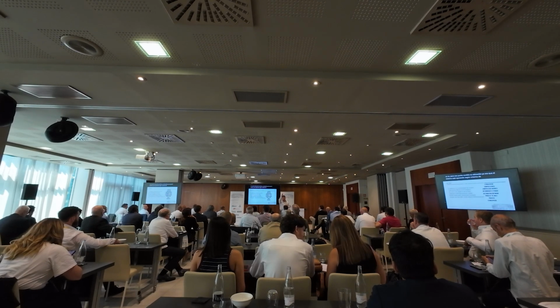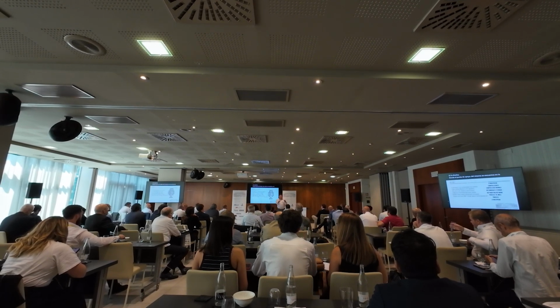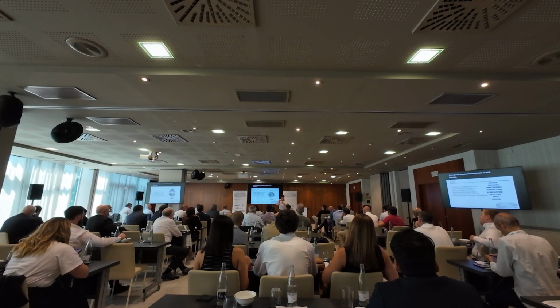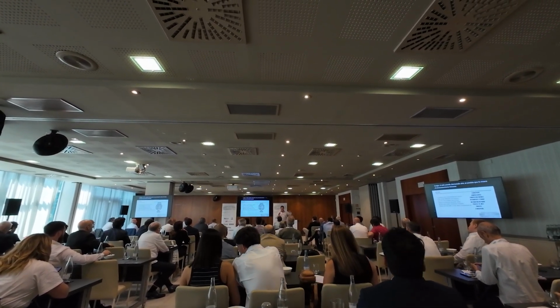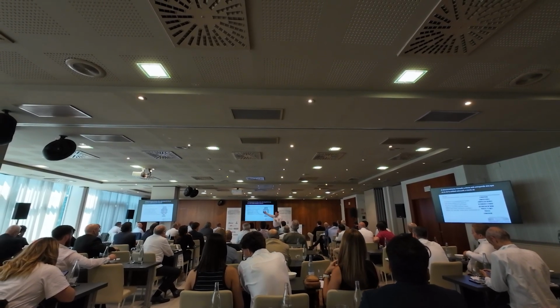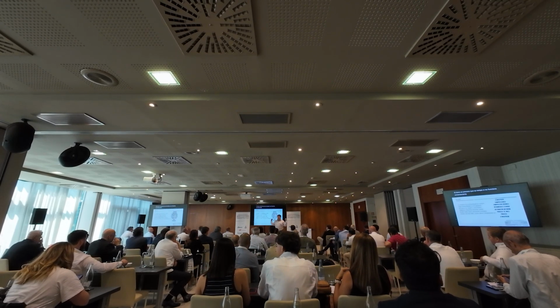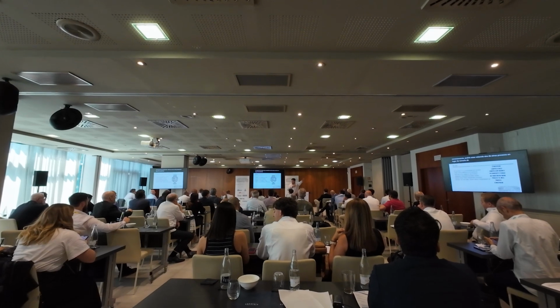If you design it where the fulcrum point of the system is at the discharge of the dry storage, primary storage, then if you're using too much air, then it might move that to the wet storage. And now you're ripping air that is not of proper quality through your system. If you have a process that breaks or isn't working right, you could be robbing air from other processes instead of taking it from the compressed air station, right?